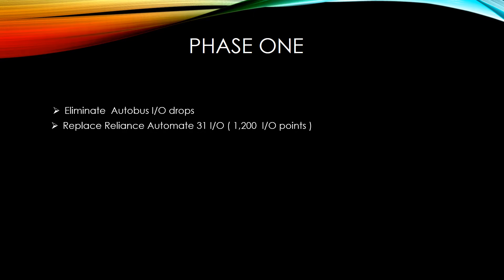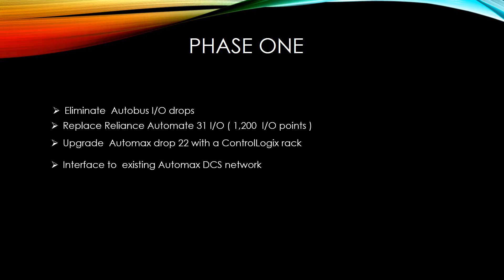In phase one, we had determined that the Autobus IO drops and the Automate 31 IO is the biggest liability on the line. So we will replace about 1,200 IO points in nine different locations controlled over the Autobus IO network. We will upgrade the AutoMax Rack 22 with a new ControlLogix processor, then interface to the existing AutoMax DCS network.